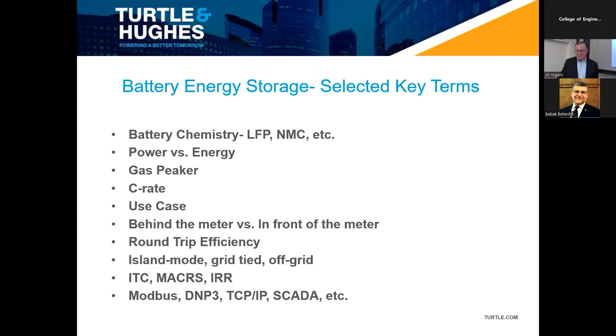Round trip efficiency, very basically, is what goes in versus what comes out. Lithium ion tends to have very high round trip efficiency, and I'll show you why that's important here in a minute. These systems can be islanded, which means disconnected from the grid - they can be completely off the grid, in the case of Richard Branson's island where there is no grid, or they can be grid tied, where they operate in concert with Long Island Electric, for example, or PSE&G Long Island.